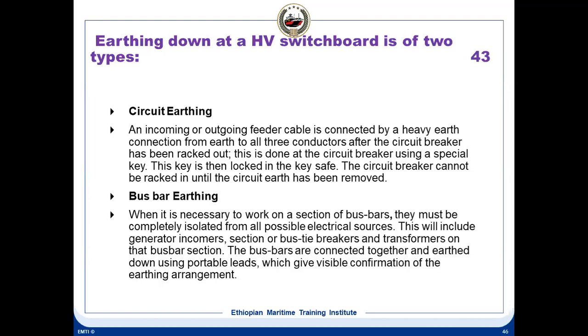They are supplied with 3 portable leads: 1 lead for R phase, 1 for Y phase, 1 for B phase, connected on the 3 busbars, and 1 common ground at the bottom. So you can make a grounding. That is called busbar earthing, circuit earthing.